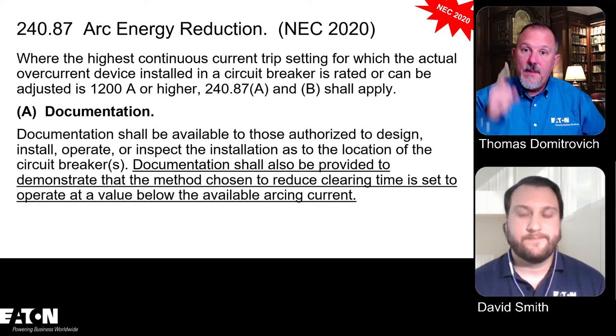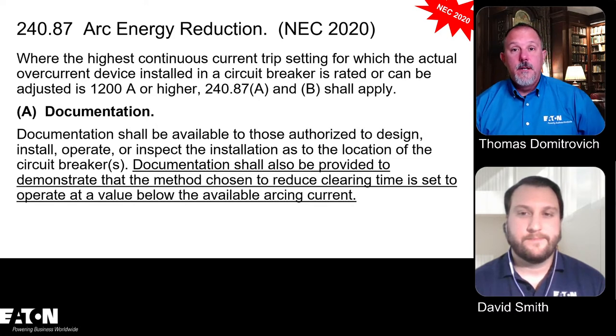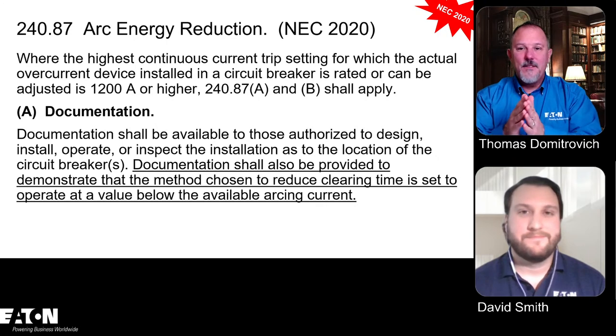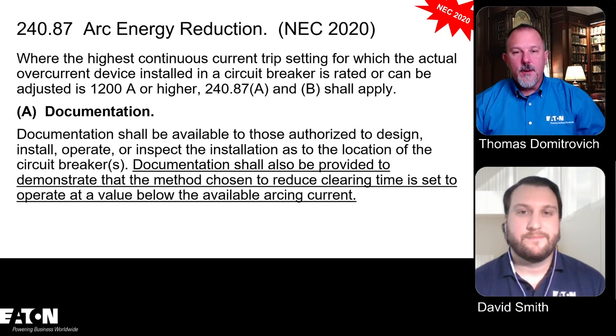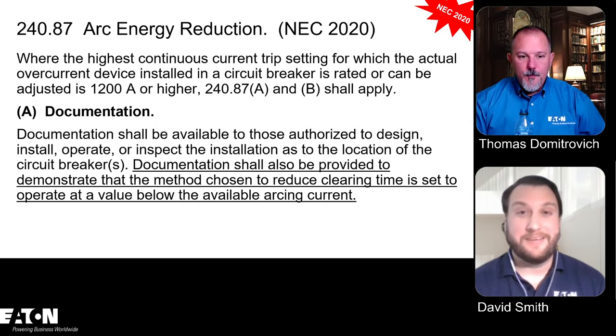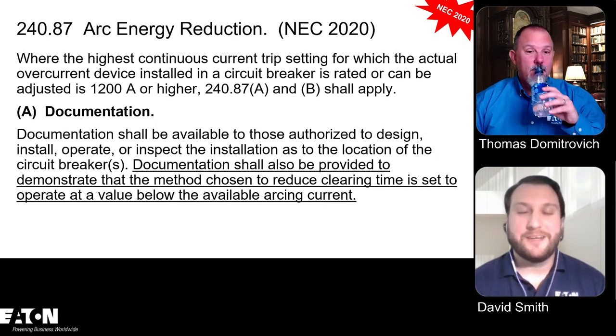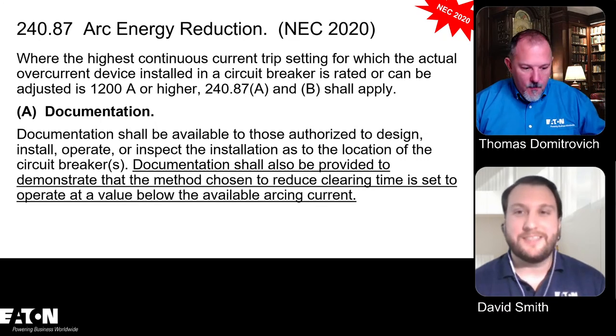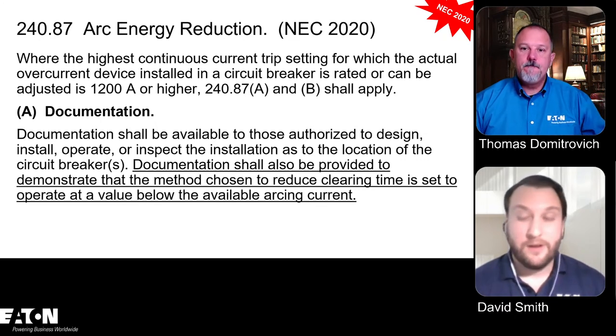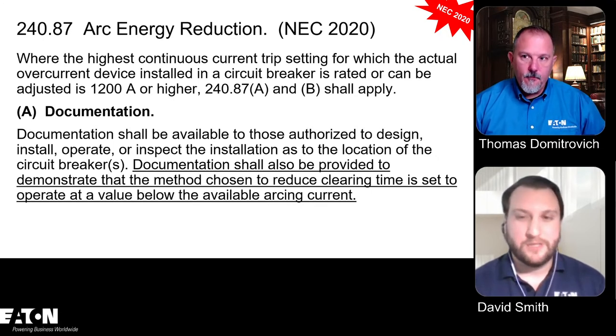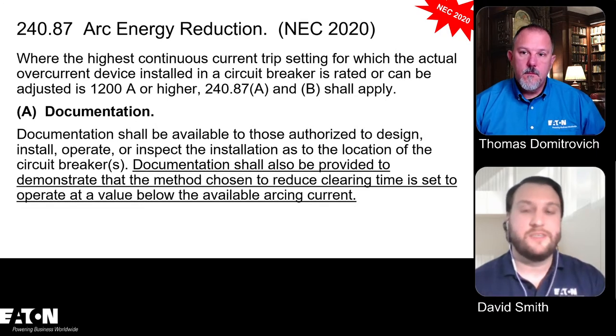Absolutely. Now, what this is dealing with, I don't have to do all that. 240.87 doesn't care about incident energy. Although the title is incident energy reduction, there's no numbers on incident energy. It's all focused on the clearing time of the arcing current. Why? Why does it have to do with the clearing time of the arcing current? Yeah. What we talked about before, right? It's because there's less energy, so the circuit breaker is going to take a little bit more time, depending on what it is. But you just want to make sure that that circuit breaker is prepared for that minimum amount that could still be dangerous.